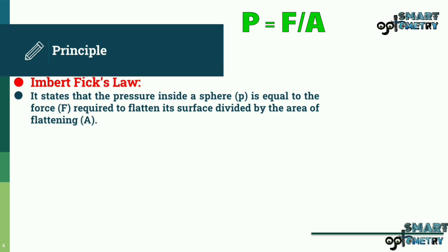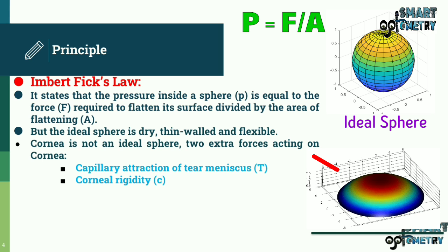The Goldmann Applanation Tonometer is based on the Imbert-Fick law, which states that the pressure inside a sphere is equal to the force required to flatten its surface divided by the area of flattening — that is, P equals F divided by A. However, the ideal sphere is dry, thin-walled, and flexible, and the cornea is not an ideal sphere.